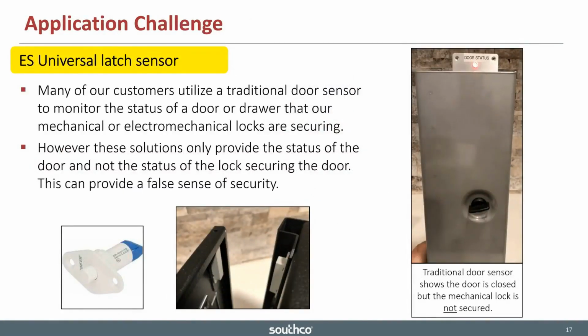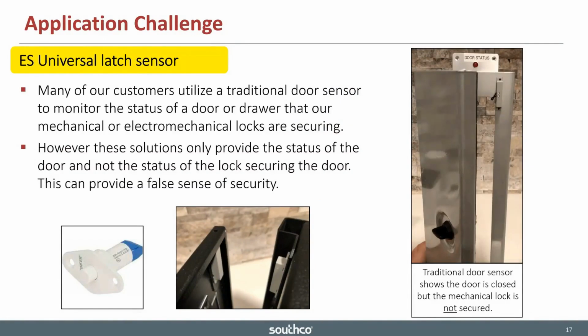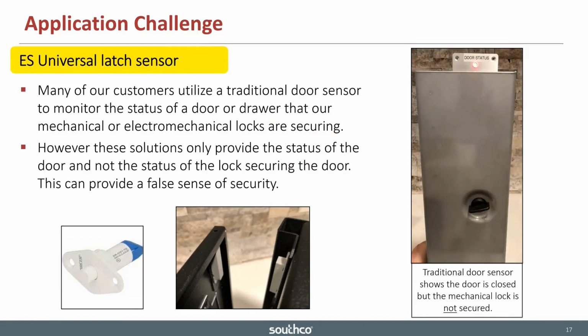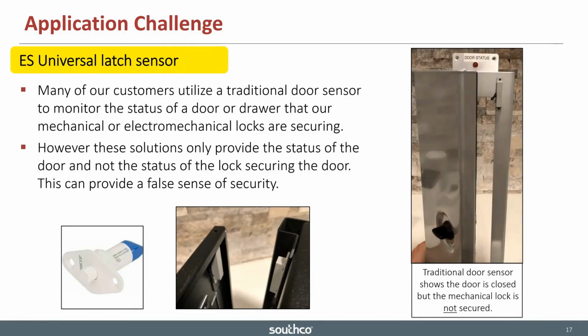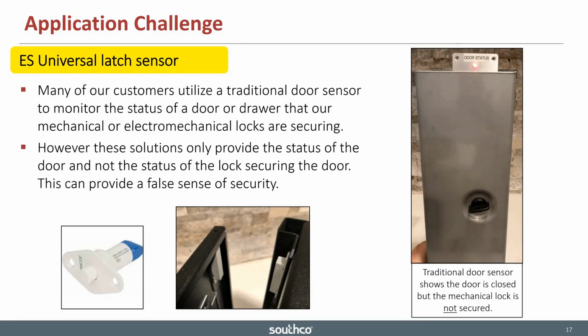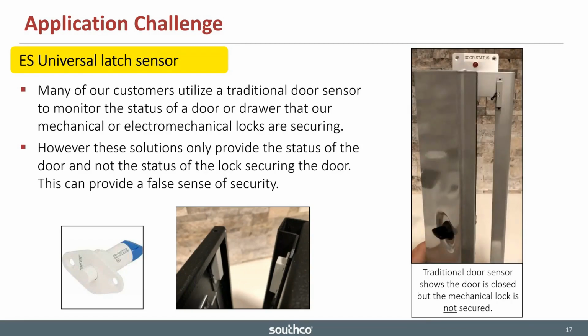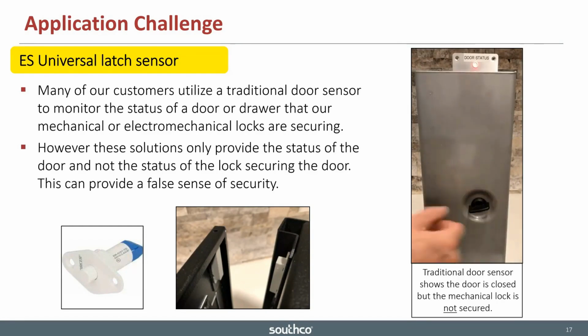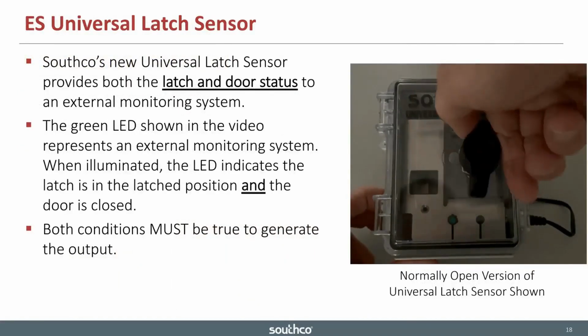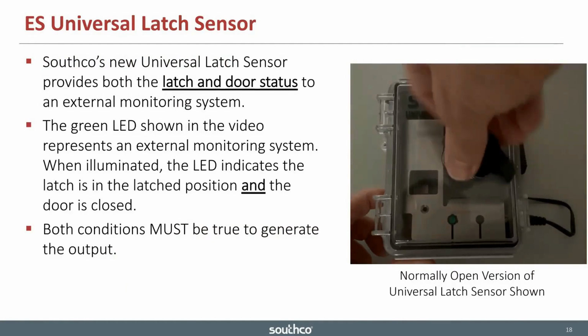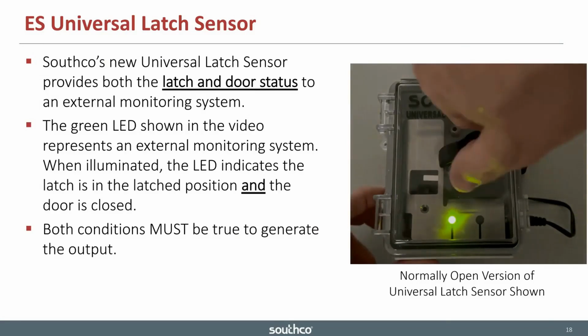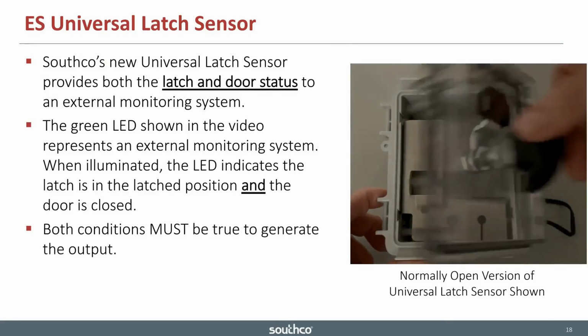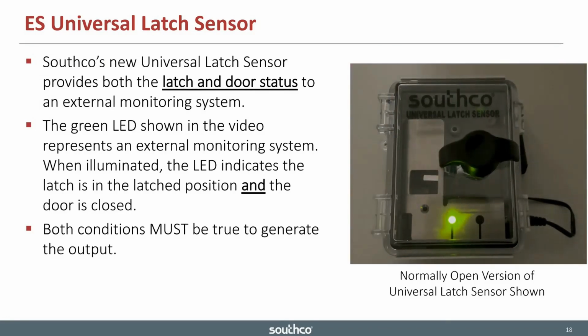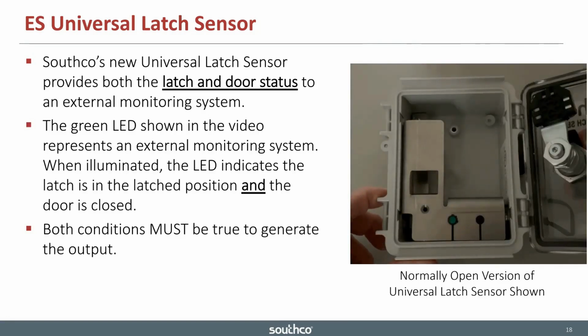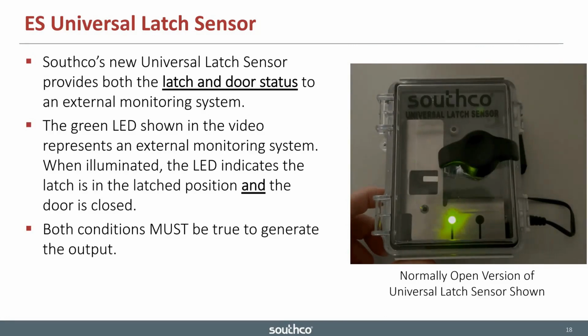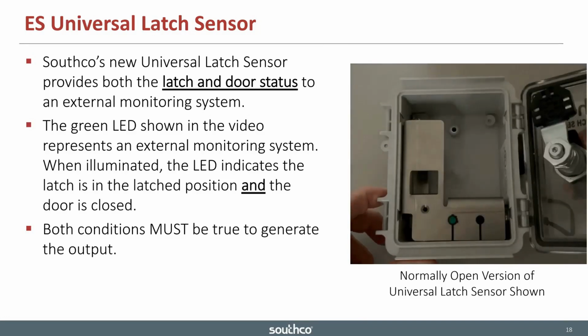And one last one that we will go through is an add-on feature to mechanical locks, and it's what we call a universal latch sensor. So predominantly people will use push switches or magnetic sensors that will sense the door position and tell you I'm closed, but it does not sense the latch position. So in this animation, you can see that the output signal is only completed when the latch is rotated so that the magnetic pole is in close contact with the reed switch. At that point, you get the signal that I'm secured correctly. And this can be a retrofit or an add to a range of standard mechanical locks.